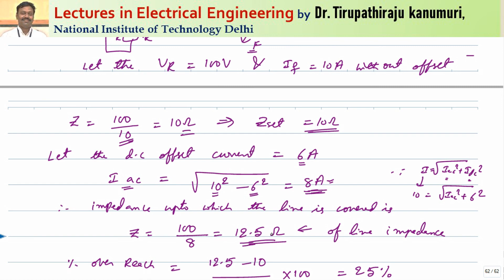Because the farther the fault happens, the lesser will be the fault current, you agree with me? So it is operating even for 8 amperes, or it will operate up to a line impedance of 12.5 ohms. That means on the transmission line, if you are taking 1 ohm per kilometer, it will protect up to 12.5 kilometers instead of 10 kilometers. This is called the percentage overreach of the relay. That's why the relay should have a proper design to overcome this transient overreach.